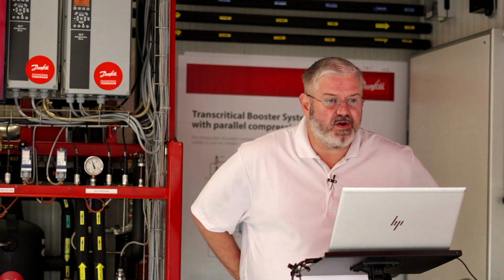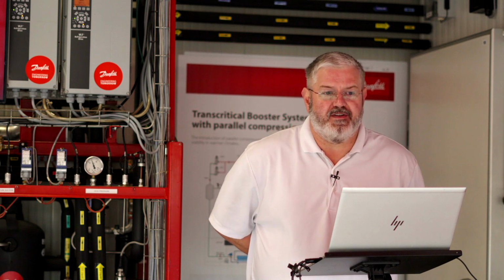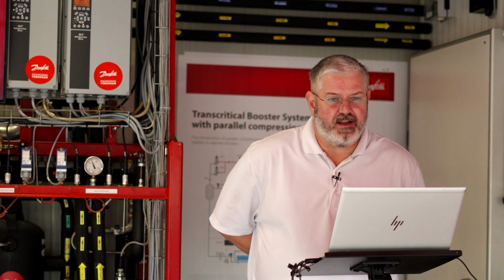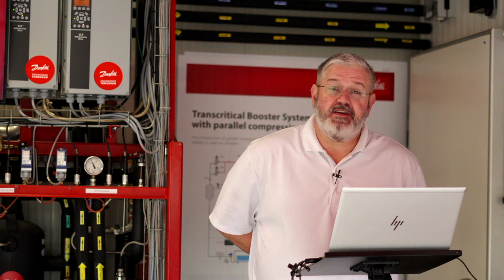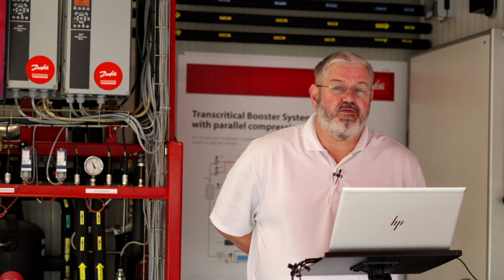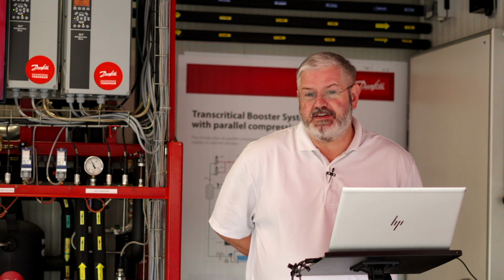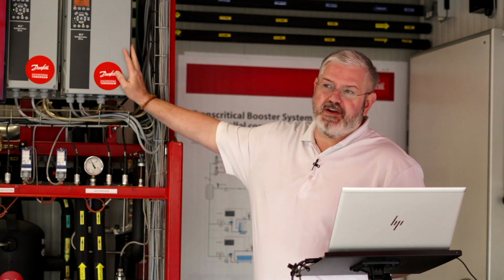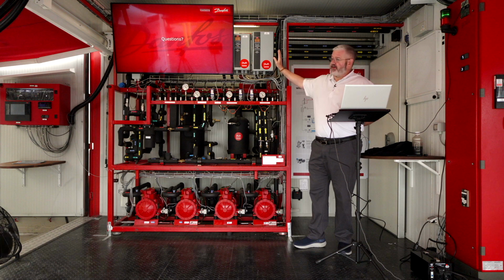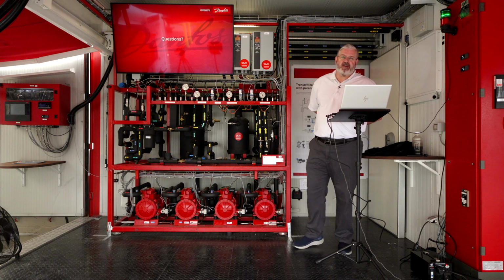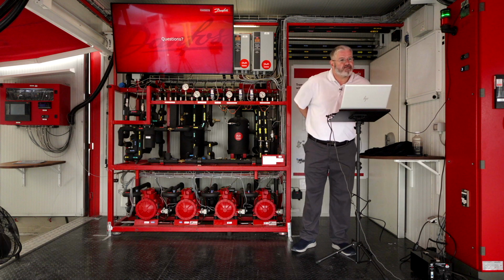Okay, so we have a question on can you use Modbus on the VLT drive instead of analog signal? I believe the answer to that is yes. We typically use 0 to 10 volt as our default. We don't want to lock people into Modbus, like you have to use our product. We want you to, and our products are wonderful and amazing. They bring me happiness. But should you choose to use our competitor, we'd like to make that easy for you. We typically default to a voltage signal.